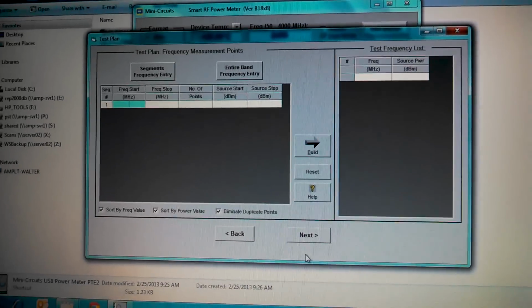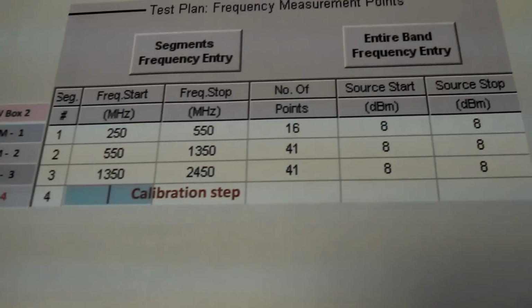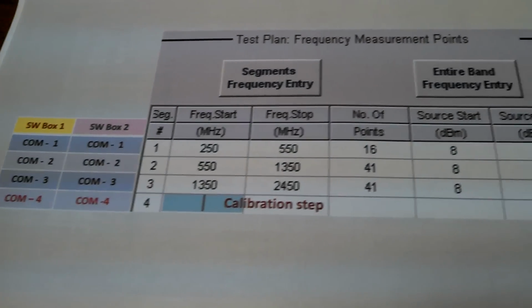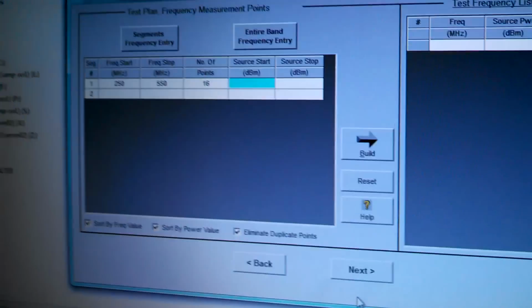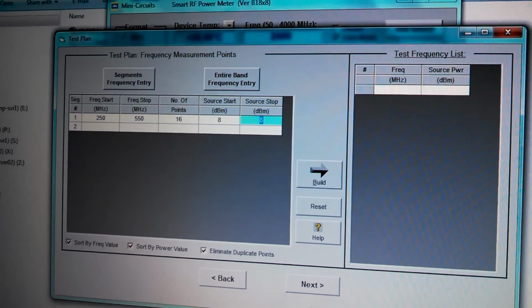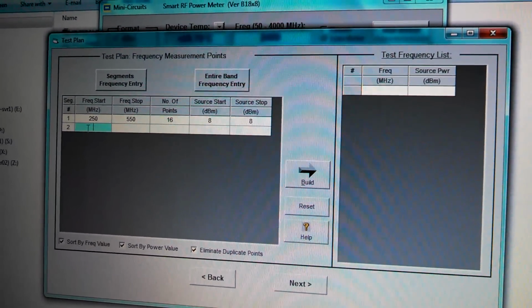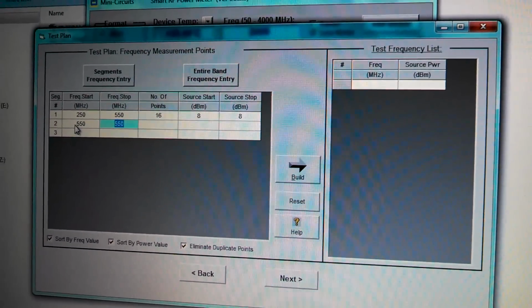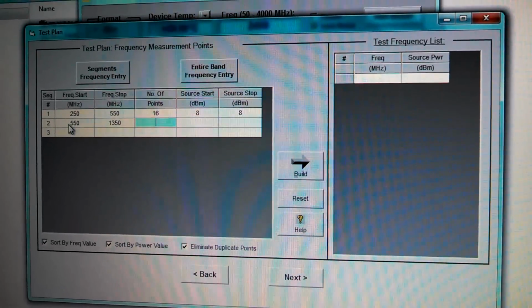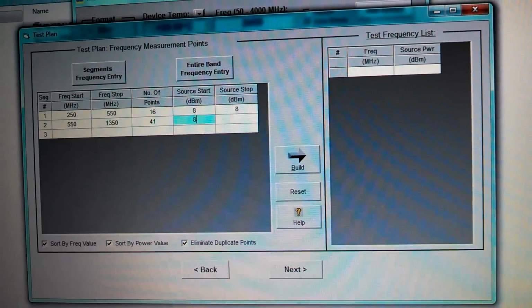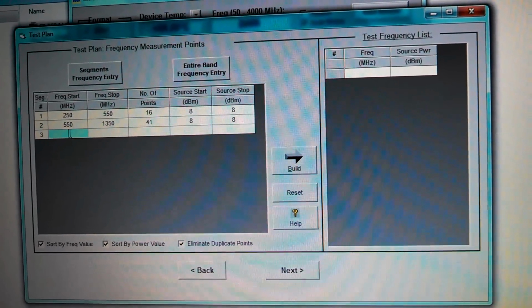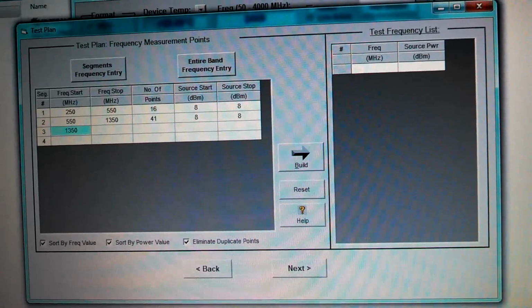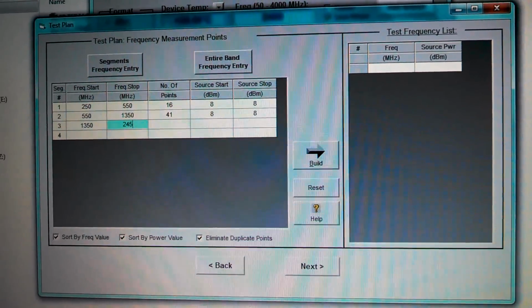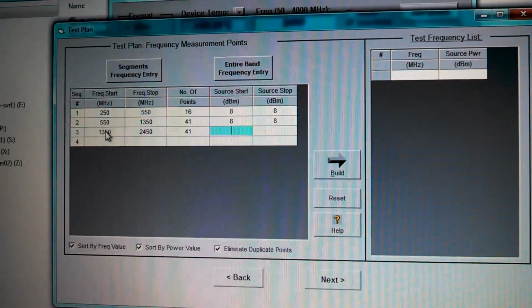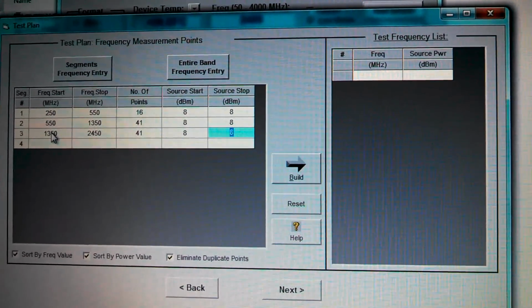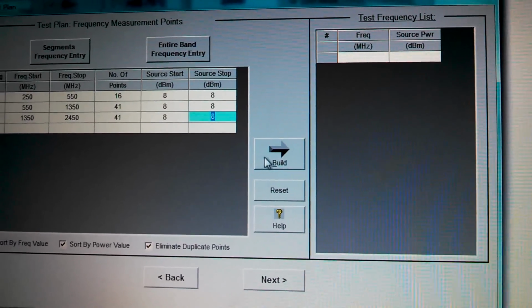Our spectrums of interest are going to be 250 megahertz to 550 with 16 points of measurement with an 8 dBm drive level for filter number 1. For filter number 2, we're going to use the 550 to 1350 spectrum using 41 points of measurement and 8 dBm drive. For the third filter, we're going to use 1350 to 2450 with 41 points of measurement and an 8 dBm drive level. So we're ready to build our frequency list by clicking here.